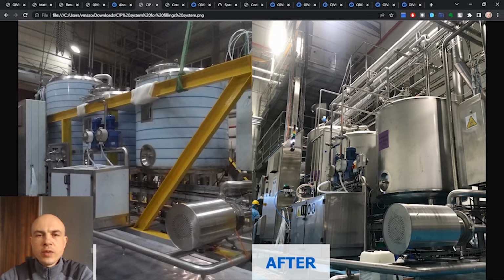As usual during startup, many issues arose - mistakes in the program, wrong communication, failures of some components. In this project, we found out that it's a big problem that you cannot observe the process on a tablet or smartphone, and you need to go to the HMI panel to investigate. I wanted to see the process from my smartphone. When a process fails, I need to spend time where the failure happens, and then spend time with the programmer to investigate what happened. In many cases, we had to repeat the process in order to repeat the failure and lose time.